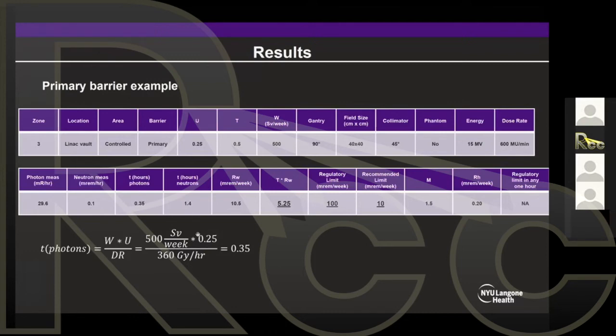And for the neutrons, I'm just going to use a use factor of 1, because they're going to come to the barrier from any orientation of the gantry, so 1.4. And now I'm going to calculate my RW, right? You're just going to multiply this by this, and this by this. You put it together, and basically the photon measurement dominates this, you get 10.5. We don't stop there because if you remember, our goal is that this is lower than your design goal divided by T. So I'm going to multiply this number by T. There's the occupancy factor, 0.5. You're going to get 5.25.